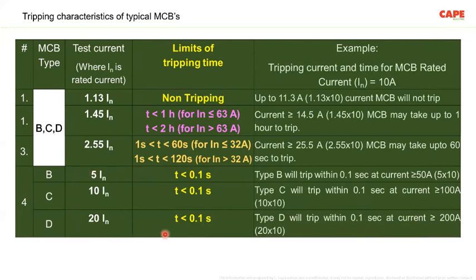And in case of quick disconnection within 0.1 second, a B-type MCB should have a minimum of 5 times its rated current during the fault or overcurrent. C-type 10 times, D-type 20 times. Based on this 5 times, 10 times and 20 times, the fault loop impedances come into the picture, because in a TN system we are supposed to use the MCB as the primary earth fault protective device. Of course, RCDs are an additional protective device.